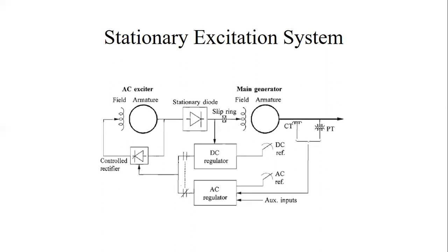The exciter is self-excited with its field power drawn through the thyristor rectifiers. The voltage regulator draws its power from the exciter output voltage. An alternative form of the field controlled alternator rectifier system uses a pilot exciter as the source of exciter field power.